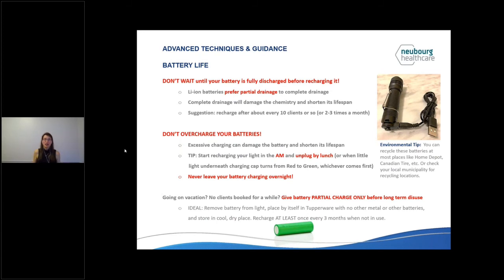troubleshooting tips. The number one battery maintenance tip I would like for everybody to understand is don't completely drain your battery until it's dead before recharging it. We use lithium-ion batteries, which are like the batteries in our phones, and a lot of people actually don't know this, but your phone lithium-ion battery also doesn't like to be completely discharged until it's dead before you bother plugging it in.